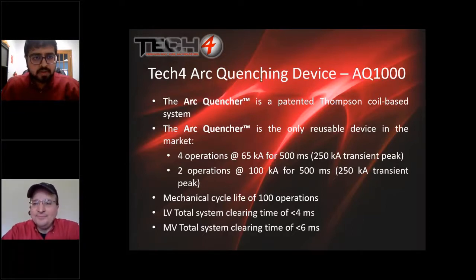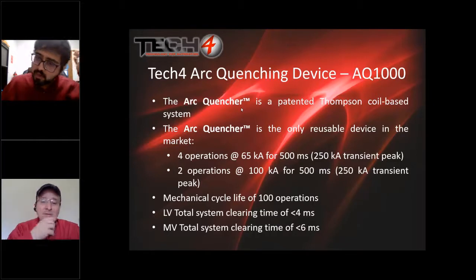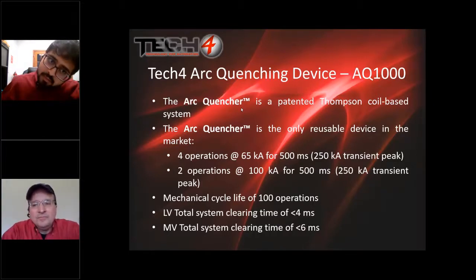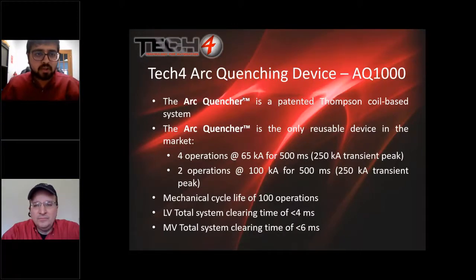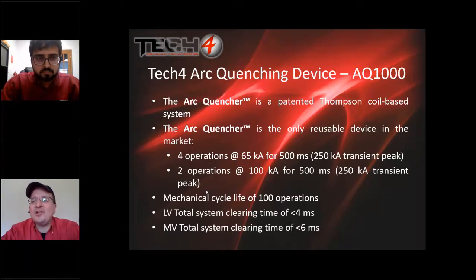Yeah, I also see a question from Shyam. I think it was the same question about the arc quencher being resettable. Yes, it's resettable after it takes the hit. After the quencher quenches once, after an arc flash event takes place, you can reset it, and it can work for another. If an arc flash event happens again, the quencher is again live and active. For testing purposes, you can test the arc quencher in terms of closure operation 100 times. You're going to test it probably a couple of times during initial commissioning, and then once every 3 years after that. So it'll last a long time with 100 test operations like that.